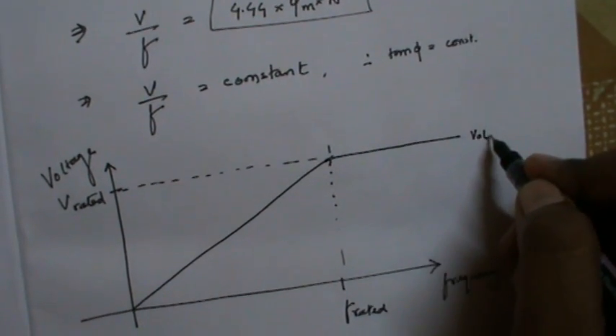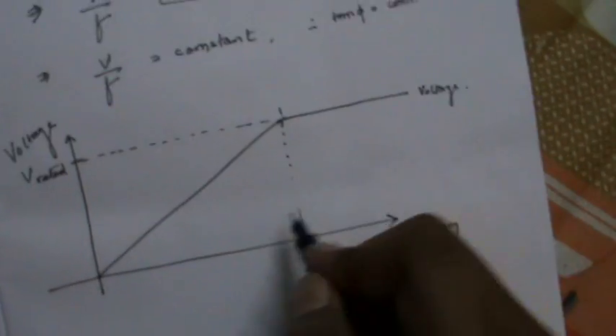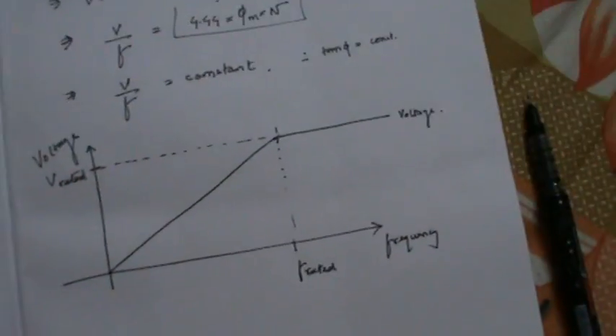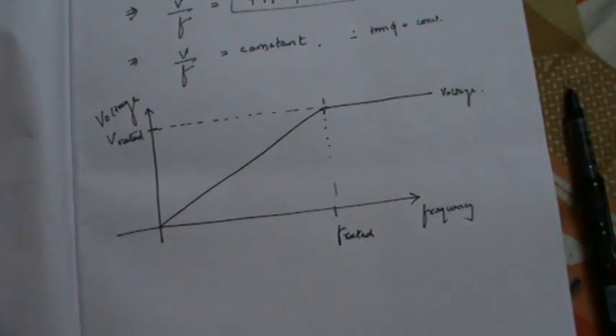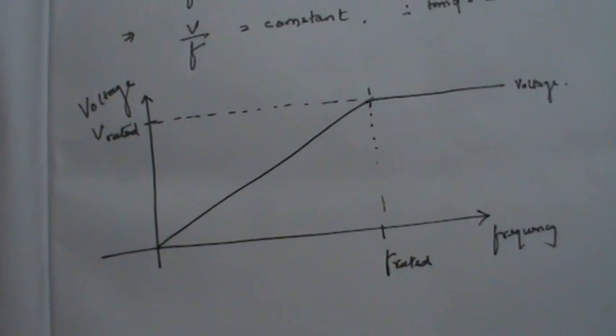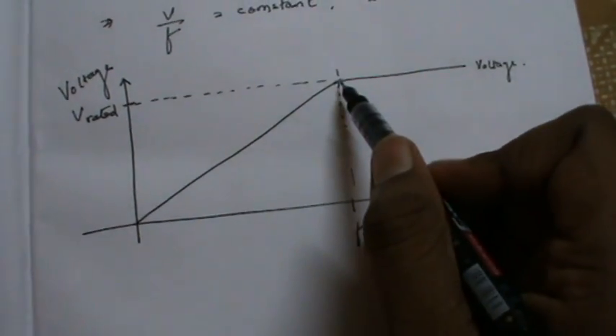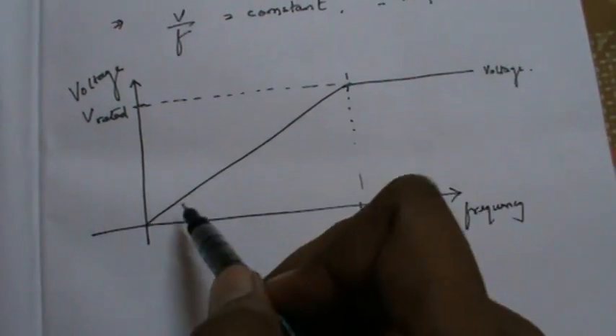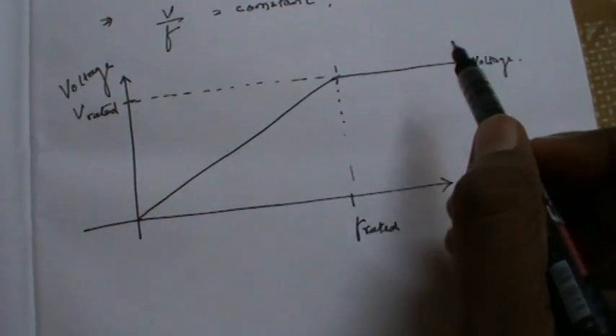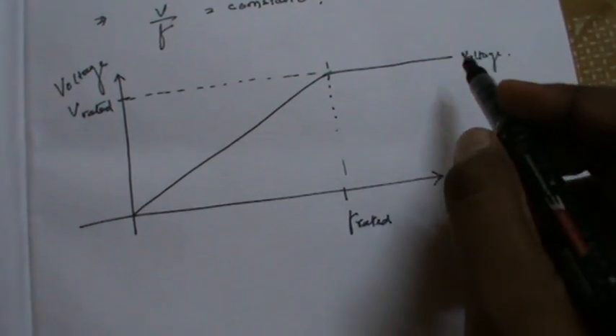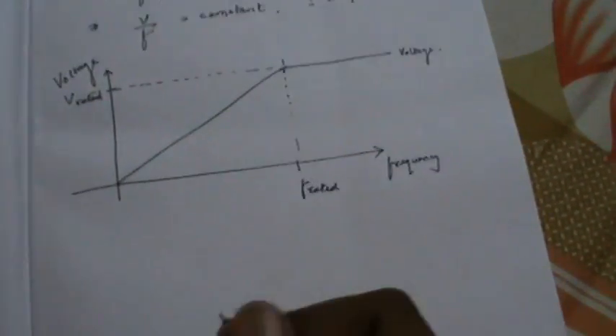This is the voltage curve plotted against variable frequency. As you can see, when the frequency is increased up to the rated value, the voltage increases proportionally. Beyond the rated frequency, however, the voltage remains constant. This is the characteristic curve of V by F control of a three-phase induction motor.